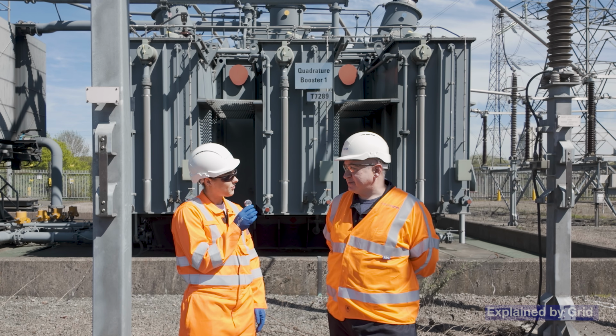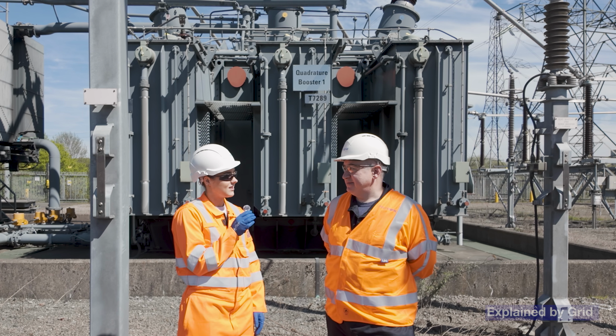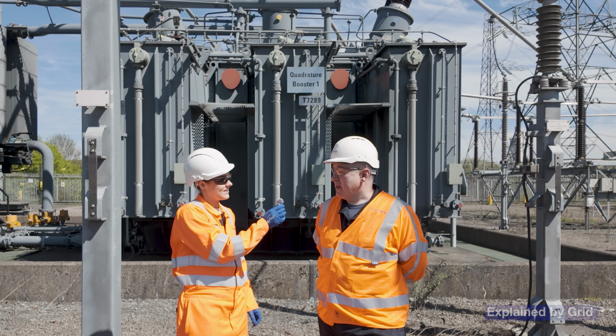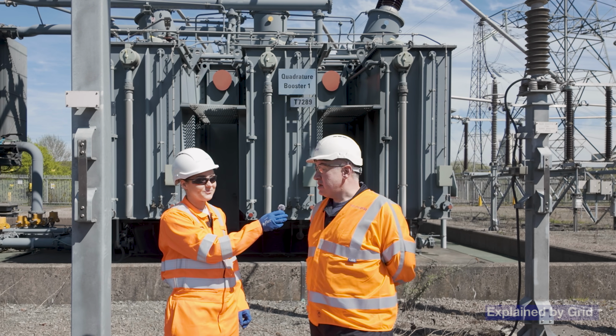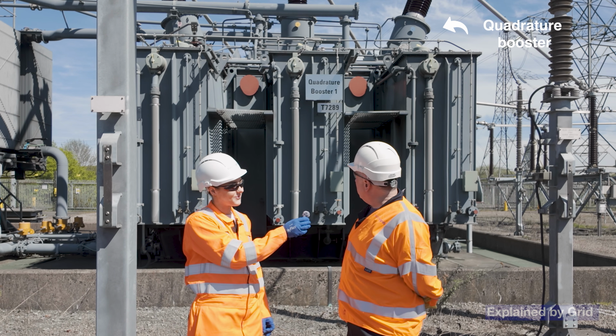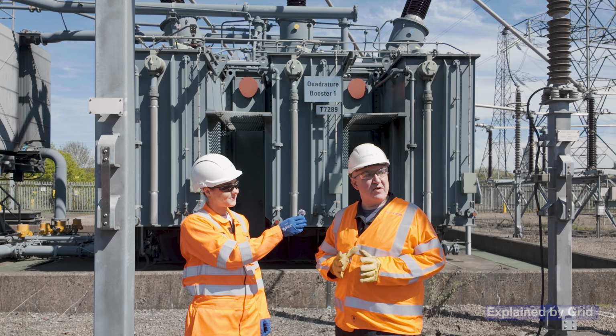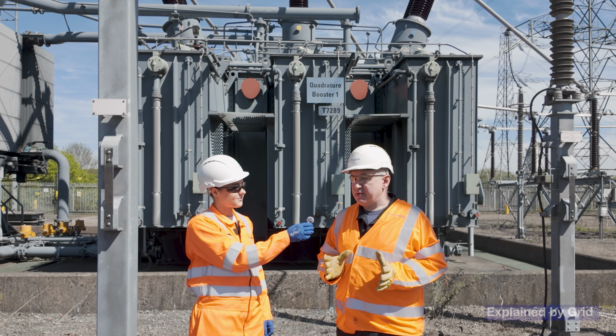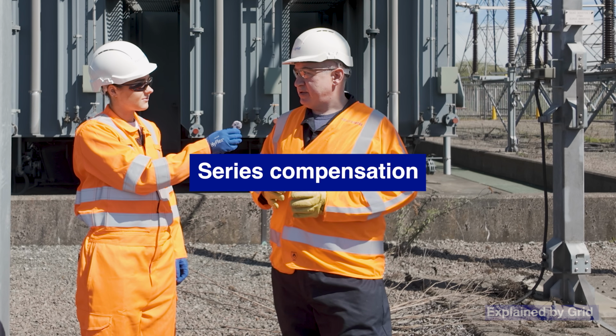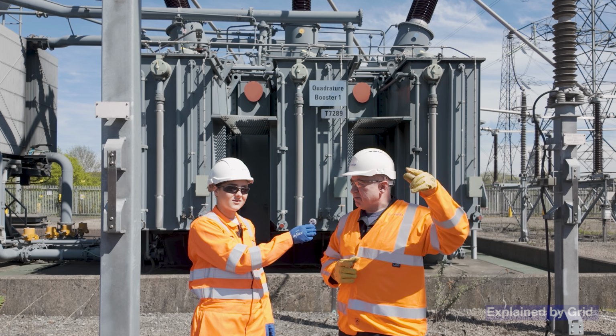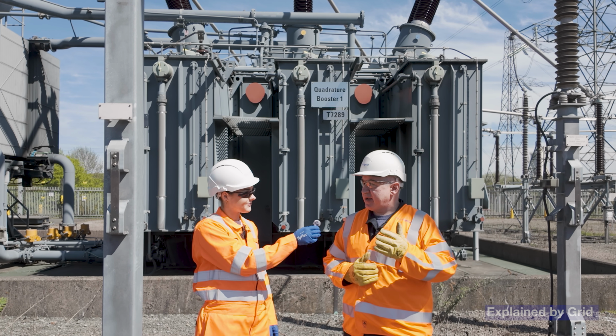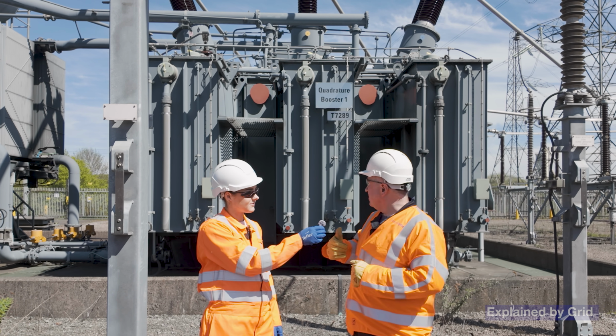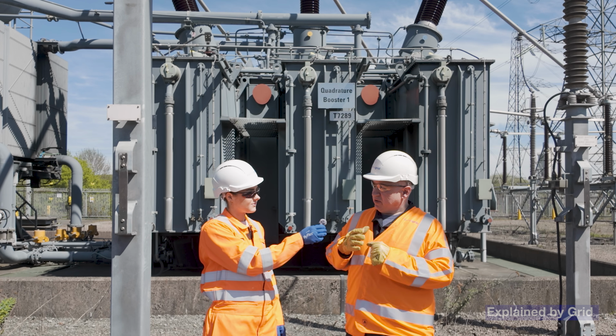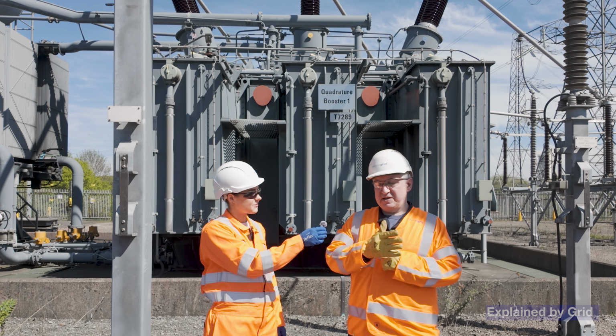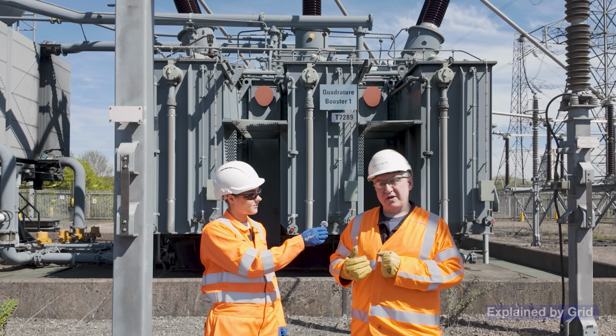So we're on to our fourth and final main function of the substation. Can you tell me what we're looking at here, James? We are looking at a quadrature booster, part of a series of elements known as series compensation. We talked about shunt reactive compensation with a capacitor bank—that's changing the voltage. What a quad booster does is change power flow into and out of the substation.